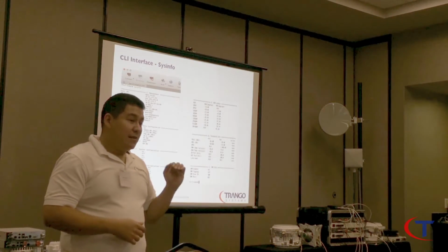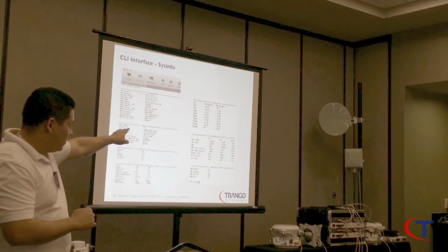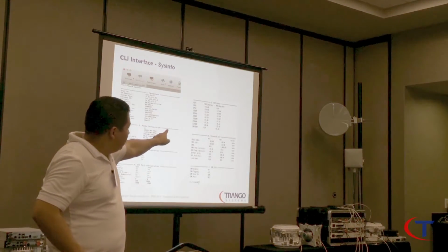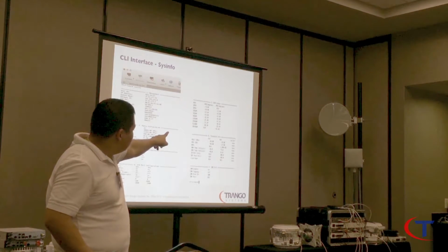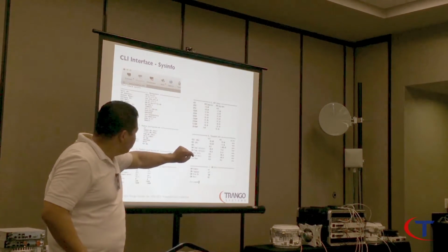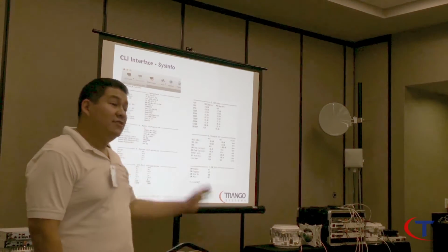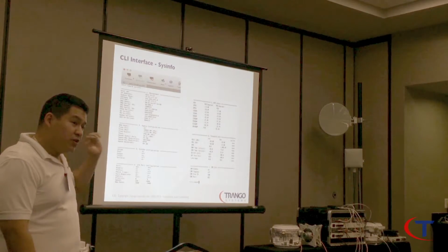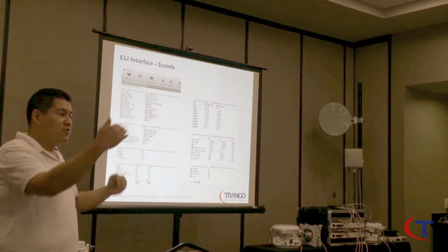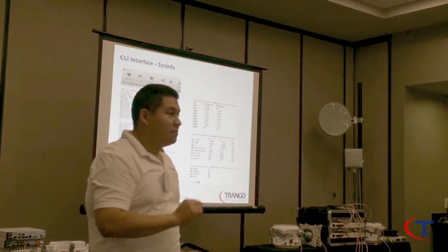The MSE dictates the modulation. So for a 1024 QAM link, my minimum MSE is going to be 35.2. That's the threshold. If it doesn't reach the MSE of 35, it's going to drop to QAM 512.